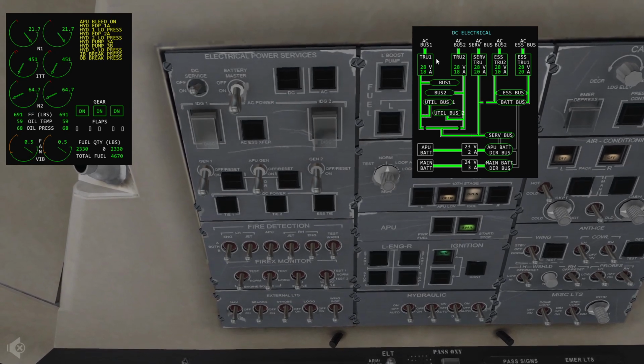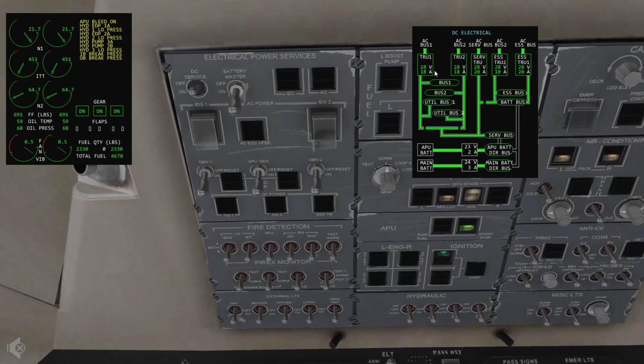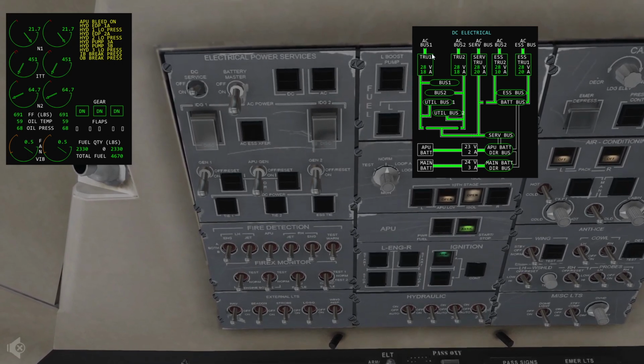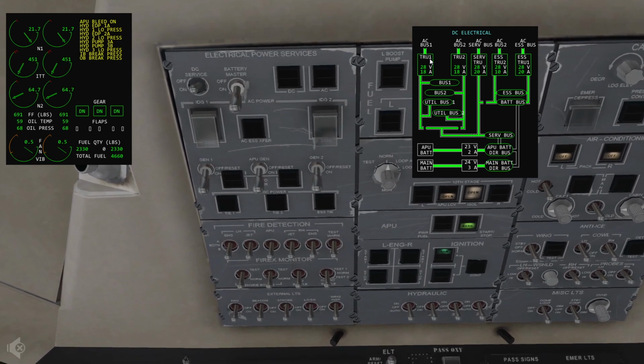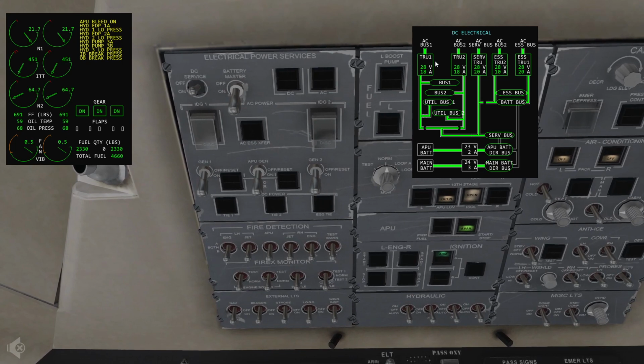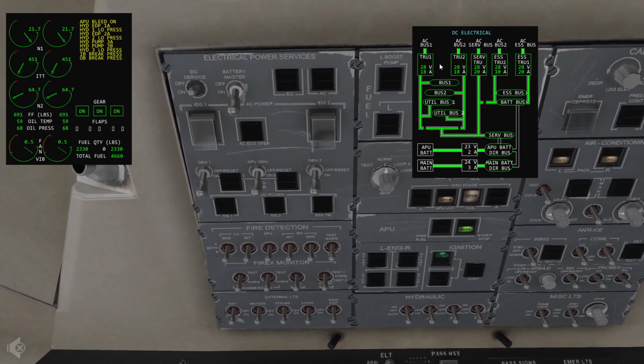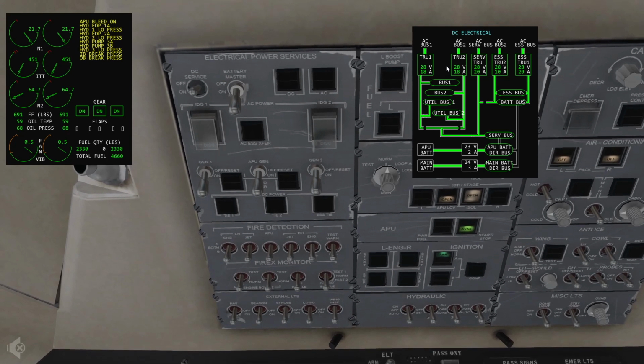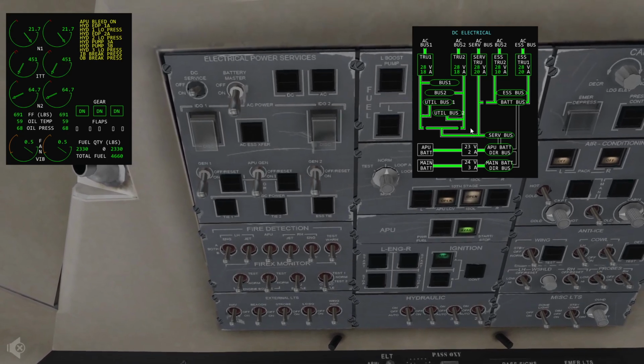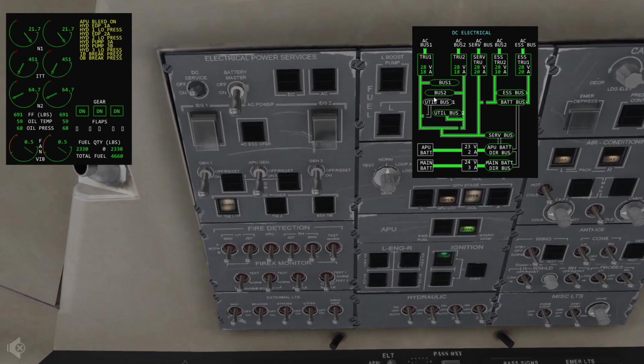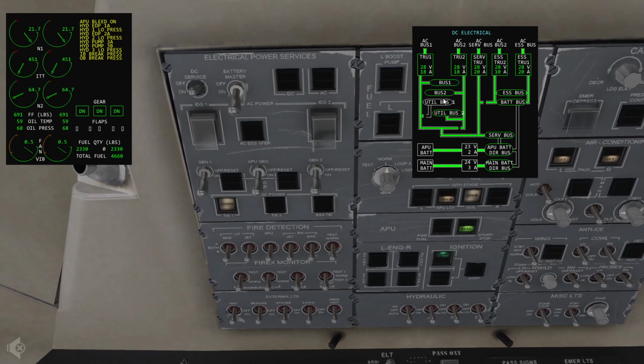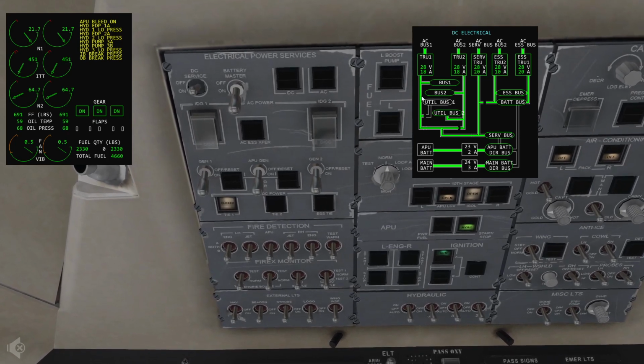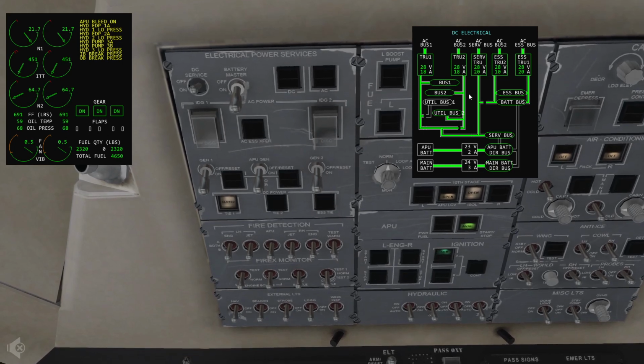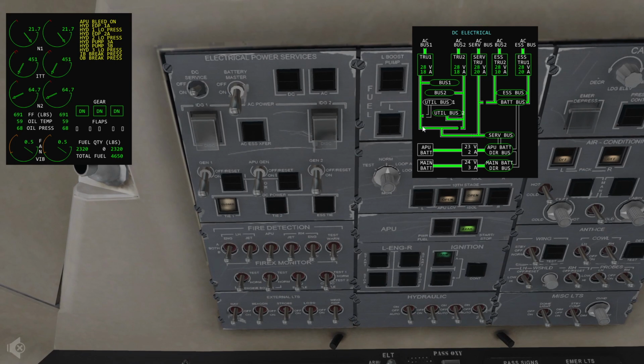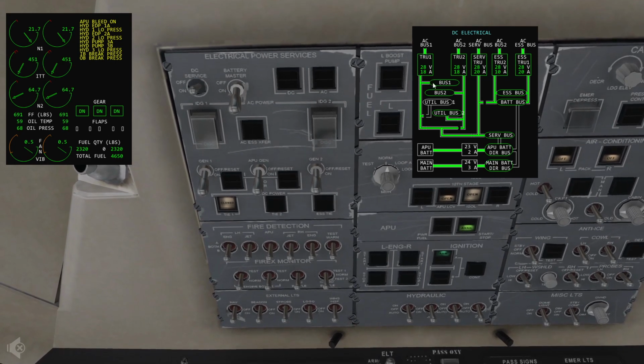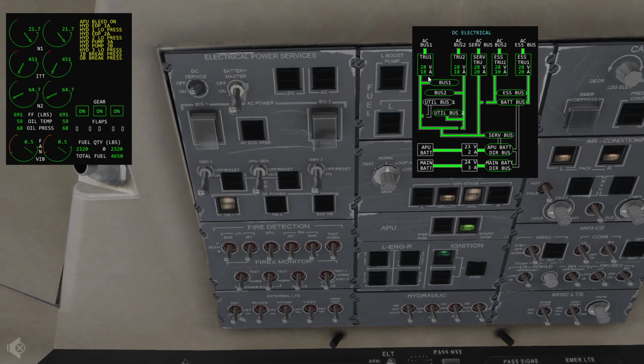So as we mentioned, again, if the TRU1 fails, in this case, going back again to this, so you guys can understand this better. The service TRU would provide power to tie 1 closing and utility bus 1 being load shed. So service TRU will power and close tie 1 and load shed the utility bus 1 in this case, and provide power to bus 1. So service TRU closes this tie 1, provides power to bus 1, and there's no TRU 1 at this point.